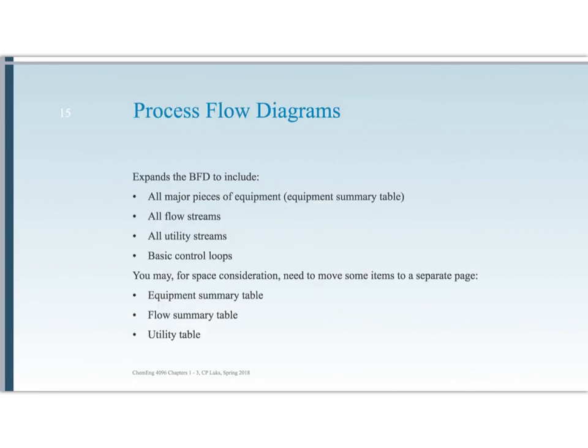A process flow diagram is similar to a block flow diagram, but it expands upon it to include all the major pieces of equipment and every flow stream. It also includes utility streams — so if I need steam to heat my reboiler, I'm going to draw that steam line; if I need cooling water for a chiller, I include that too. Basic control loops are also included, though this is not a complete control system — just the key items. Because these things get complex very quickly, some items may move to separate pages, such as the equipment summary table, flow summary table, or utility tables. All of those things need to be included, but they may not be in the diagram itself unless it's a fairly simple system.